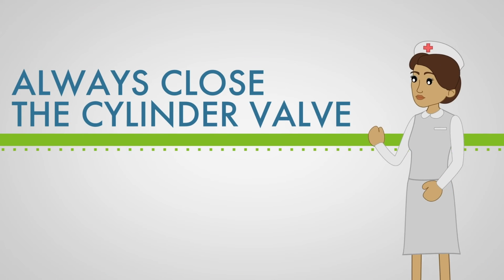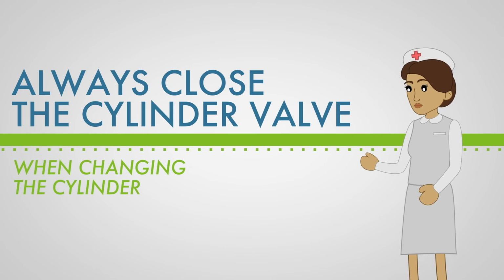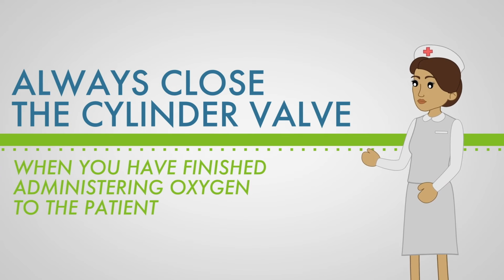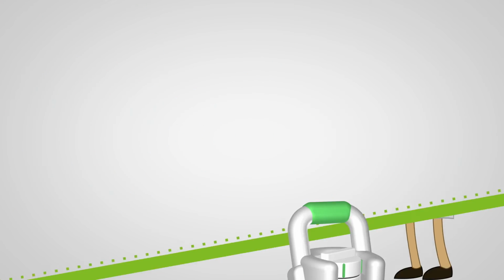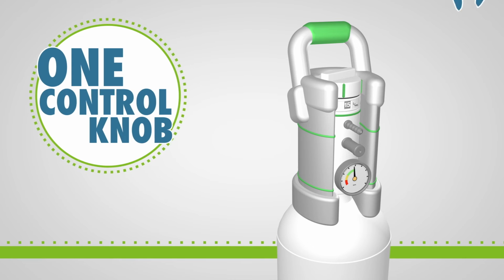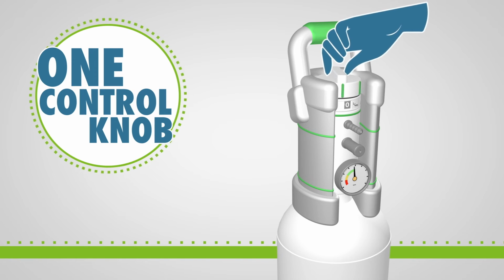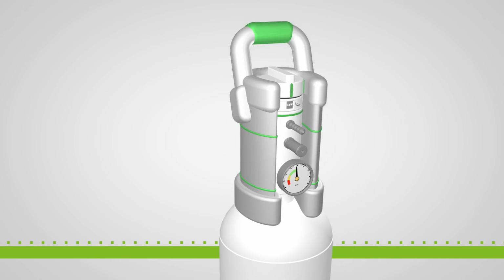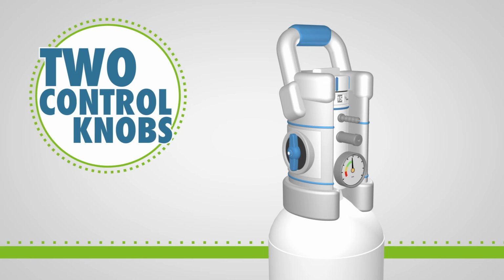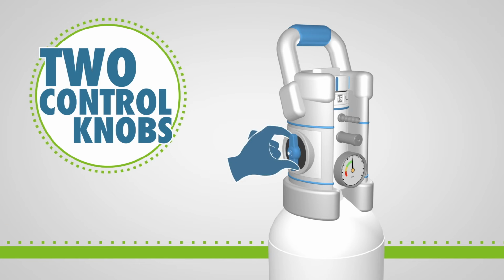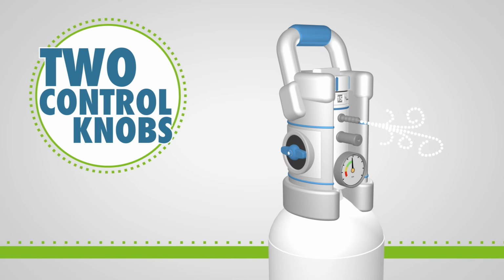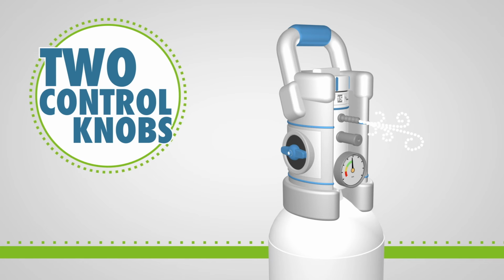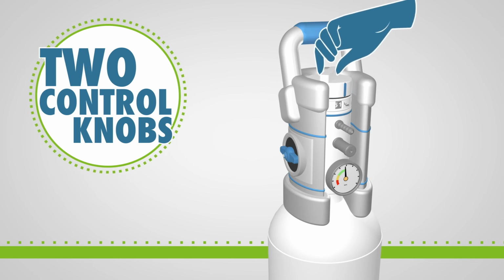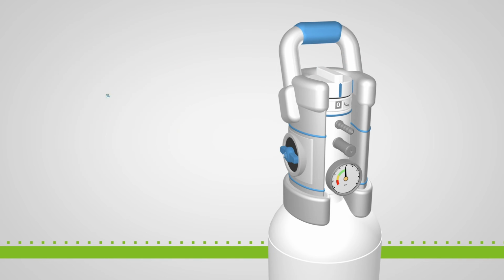Always close the cylinder valve when changing the cylinder or when you have finished administering oxygen to the patient. For the one control knob valve, turn the flow selector slowly to the off position. For the two control knobs valve, initially close the shut-off valve slowly and wait until the remaining oxygen in the valve stops flowing. Then turn the flow selector to the 0 position.